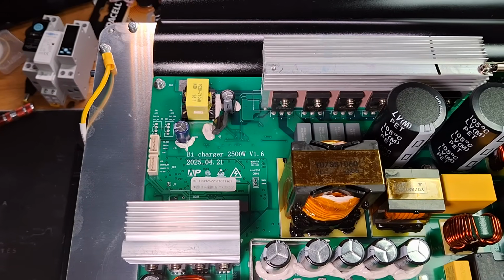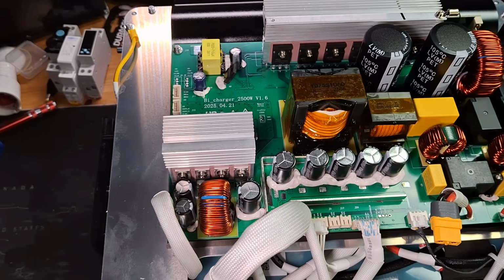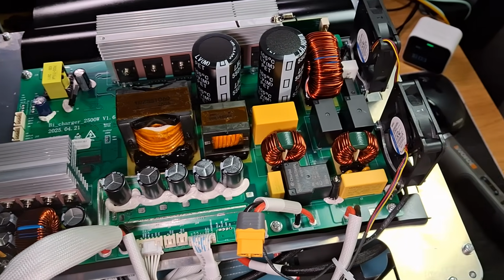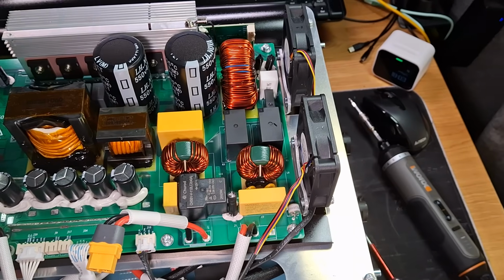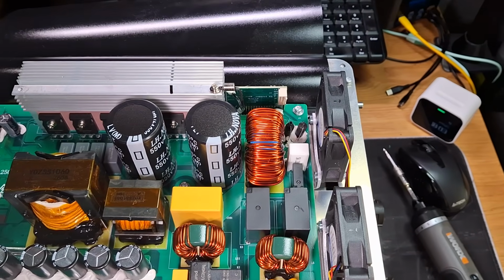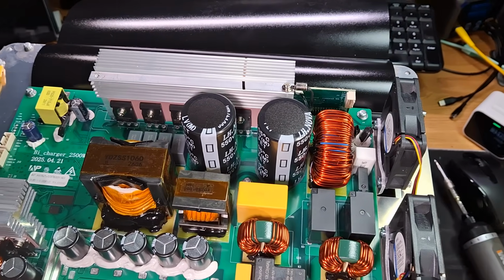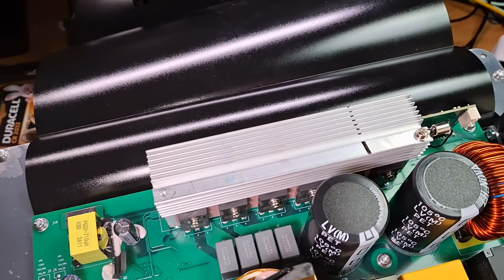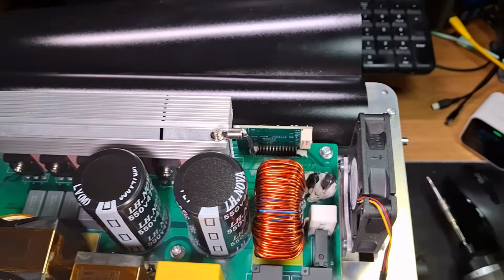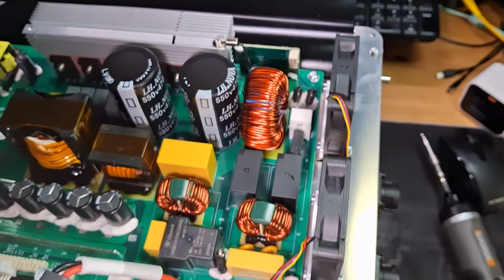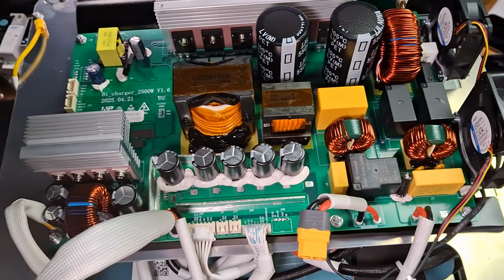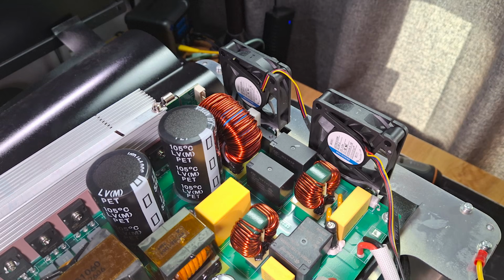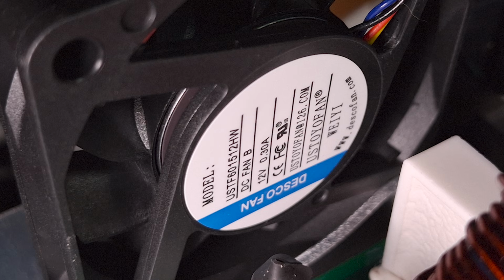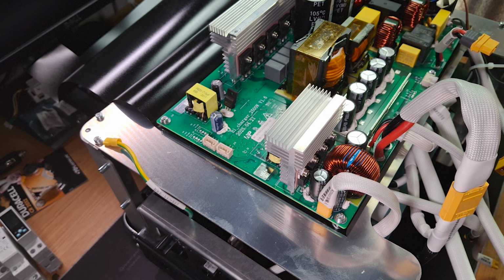Inverter board with a charger, low voltage converter, 4 transistors on a heatsink, AC input and output, and the high voltage section. Notice that for cooling this inverter, 2 small fans are used. On the other side of the board, there are unpopulated connectors for connecting 2 more fans. But these 2 fans are enough for the inverter, and that's only because the bottom metal panel on which the inverter sits is used as a heatsink.